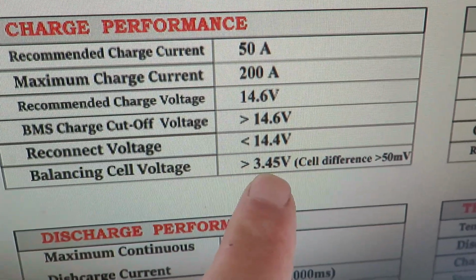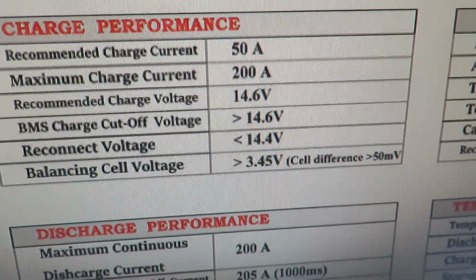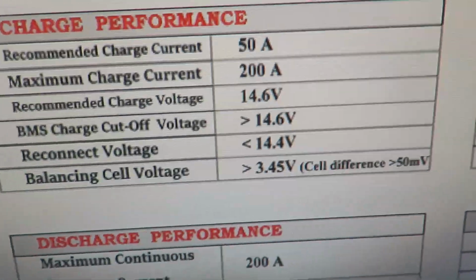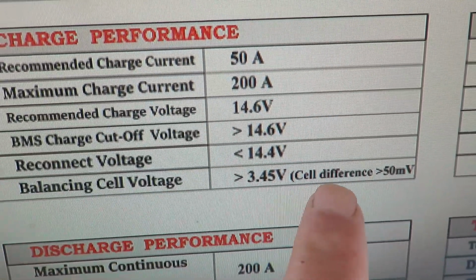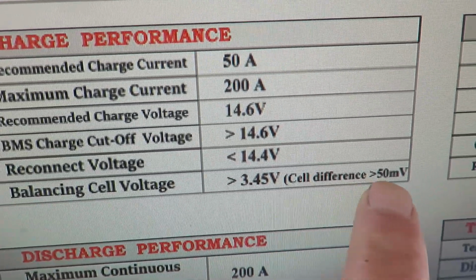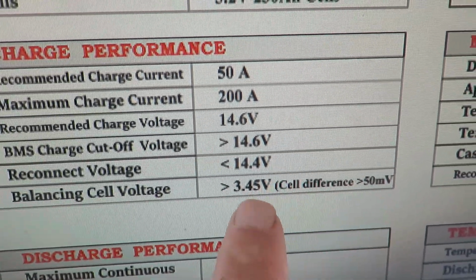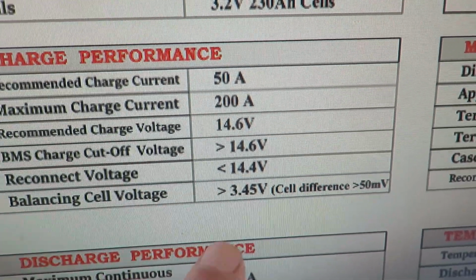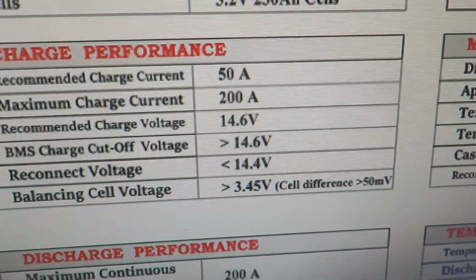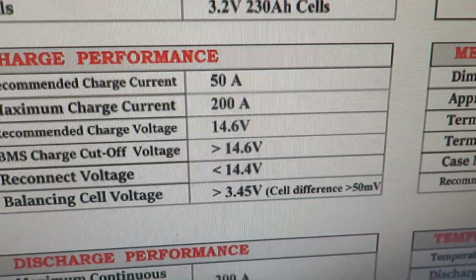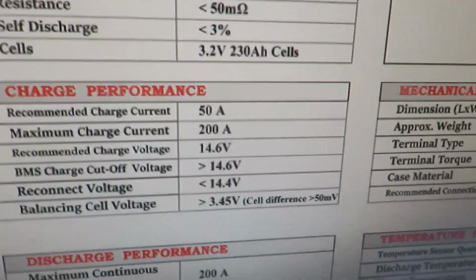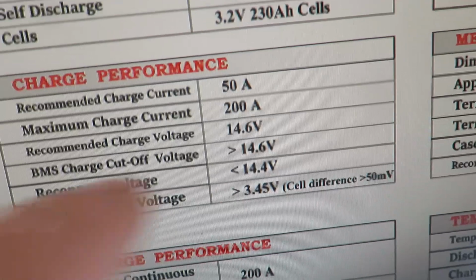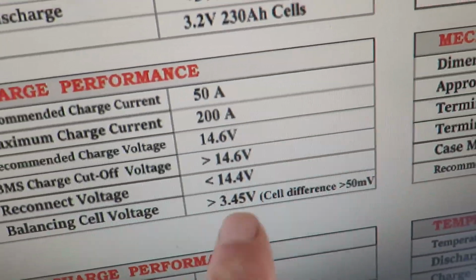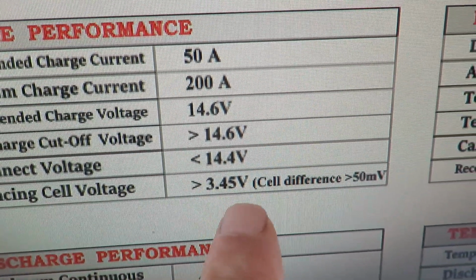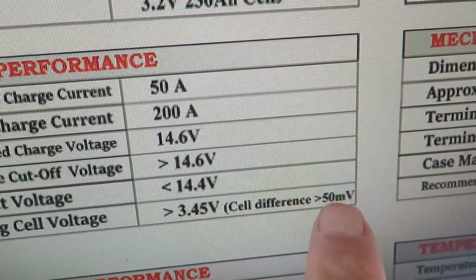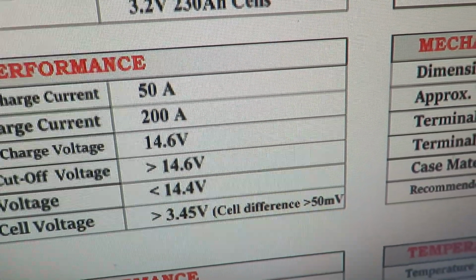3.45 volts for balancing, that's good. That's pretty much recommended by a lot of the lithium testers and experts online. And it has to be 50 millivolts different for the balancing to work. So if it gets to 3.45 volts — I have to do the math, I know all these things in my head at 48 volts — but if you get to this, it's not going to balance anything unless there's also a 50 millivolt difference between the cells.